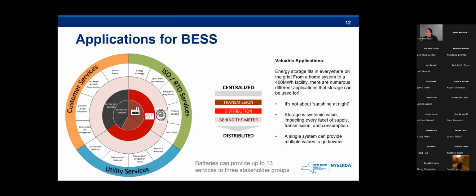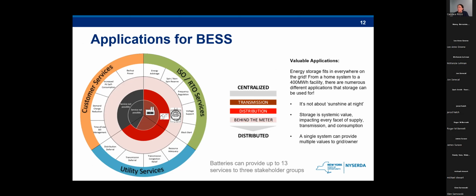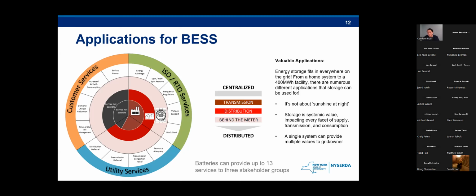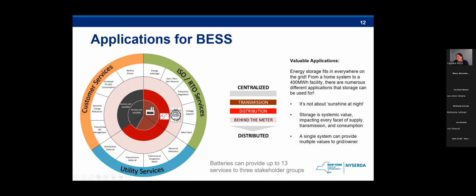Next, there are the spin and non-spin reserves. Spinning reserve is generation capacity that is online and able to serve load immediately in response to an unexpected contingency event, such as an unplanned generation outage. Non-spinning reserve is generation capacity that can respond to contingency events within a short period of time. Next, on the transmission level, storage can be used for frequency regulation. This is the immediate and automatic response of power to a change in locally sensed system frequency, either from a system or from elements of the system. Regulation is required to ensure that system-wide generation is perfectly matched with the system-level load on a moment-by-moment basis to avoid spikes or dips, which can create grid instability. So energy storage can help in that world as well.